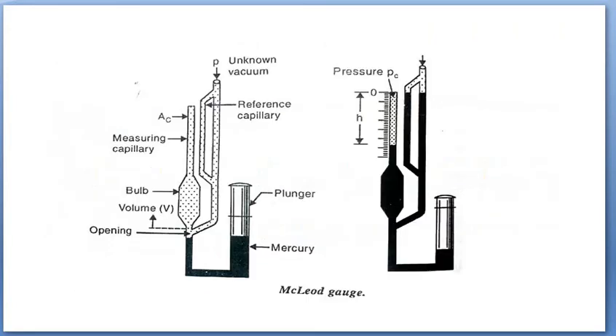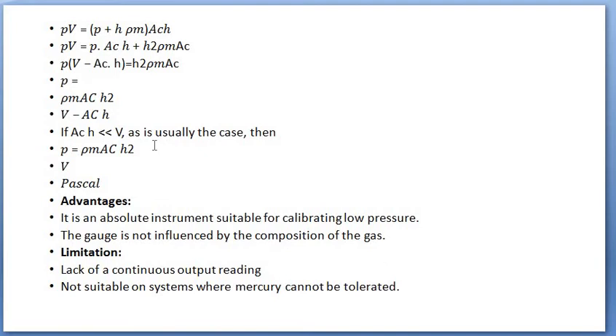So this is the concept: initially the plunger is raised, then we lower the mercury level below this, then we send the pressure down. So the measuring capillary, bulb, volume, and opening are all involved, along with the reference capillary. Finally, using the volume of gas we've sent, you find out the pressure using this formula.